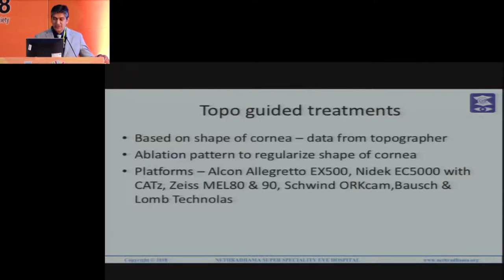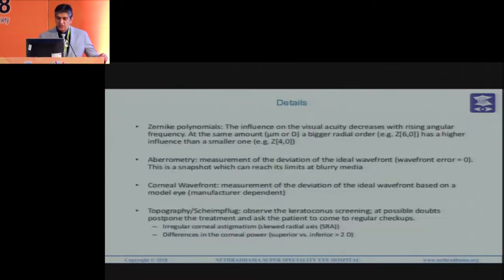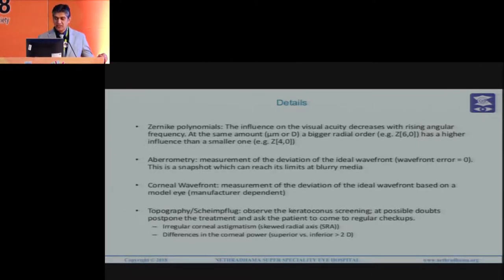Data is obtained from a Placido device, which gives more curvature data. Scheimpflug devices are used basically for screening. Higher-order aberrations are denoted by Zernike polynomials and taken into consideration while designing the treatment. The influence on visual acuity decreases with rising angular frequency, and a bigger radial order has a higher influence. The bigger radial order can be eliminated in some systems to save tissue, like in the Schwind ORK-CAM. Ideally, aberrometry measures the deviation from the ideal wavefront — with zero being ideal. Corneal wavefront specifically measures deviation from an ideal wavefront based on a model eye, which is manufacturer dependent.